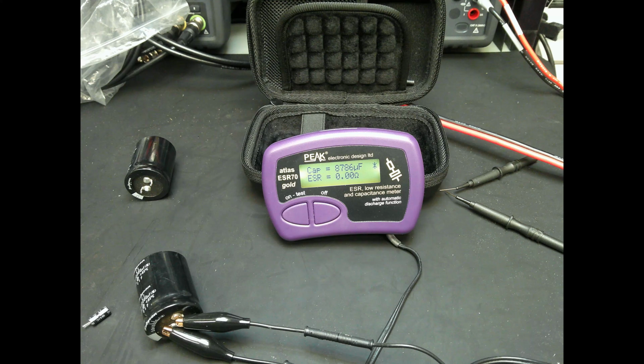What I found was that small timing capacitor had drifted off its normal value, and it probably took about 8 to 10 seconds. So I replaced it with a brand new Rubycon capacitor to pull it back to the normal timing period.